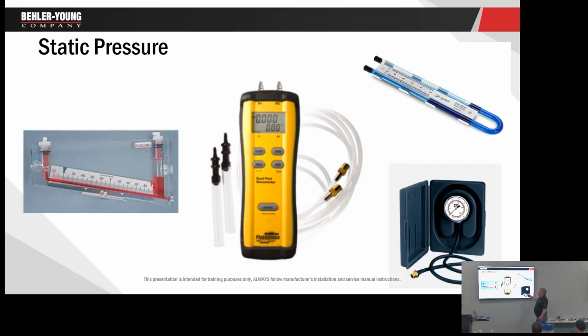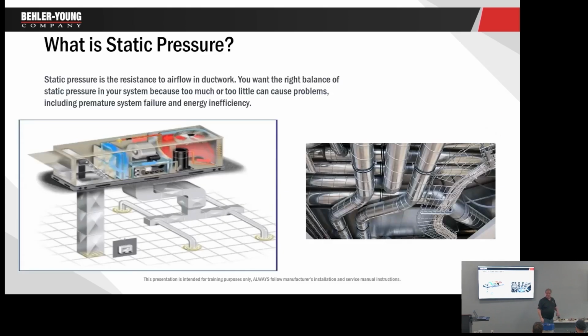Not one of these. This is fine if you still want to use one. Magnehelic, another one you might see a guy use as a big gauge like this. But a digital manometer you should have. Okay, duct system. What is static? So when I'm forcing air down a duct system, okay, every bend, every transition causes a restriction, trying to keep that air from moving. And the more restriction in the ductwork, the harder this motor has to work to push 2,000 CFM down the ductwork. So we're going to measure that resistance, static. Okay, and that's going to tell us what I need to set this thing at. So it's actually really pretty simple.